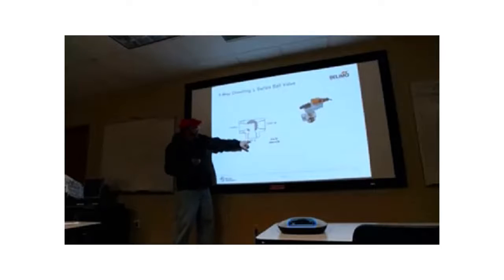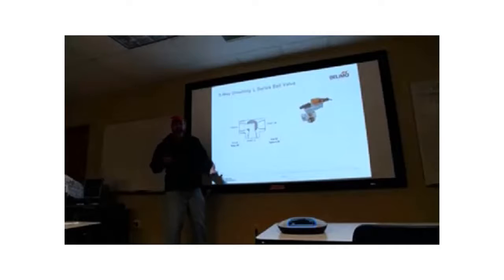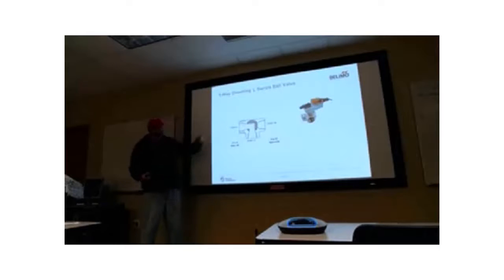Because if you notice here, we got the L here, right? Now, as we rotate this valve, this is going to get smaller and smaller, and this particular geometric situation doesn't work well for throttling. But it's fine for switching, right? Does everybody know what I mean by switching? Like, say you got a 4-pipe system, and the hot water comes in and the cold water comes in, and you want to switch between hot and cold. This is the kind of valve that you use.